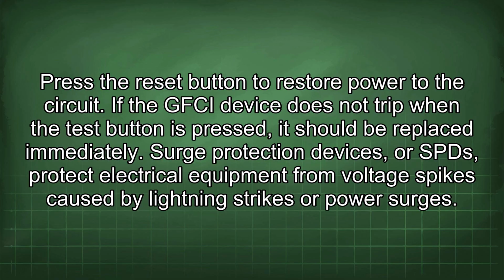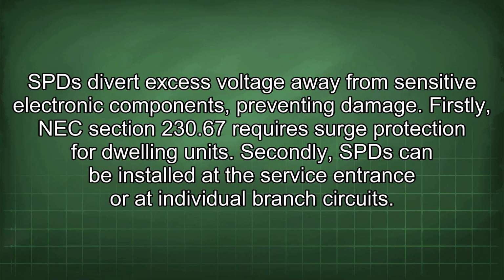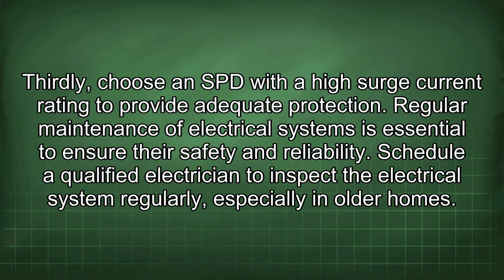Surge protection devices, or SPDs, protect electrical equipment from voltage spikes caused by lightning strikes or power surges. SPDs divert excess voltage away from sensitive electronic components, preventing damage. Firstly, NEC Section 230.67 requires surge protection for dwelling units. Secondly, SPDs can be installed at the service entrance or at individual branch circuits. Thirdly, choose an SPD with a high surge current rating to provide adequate protection.